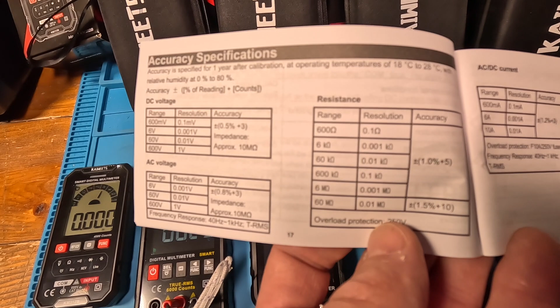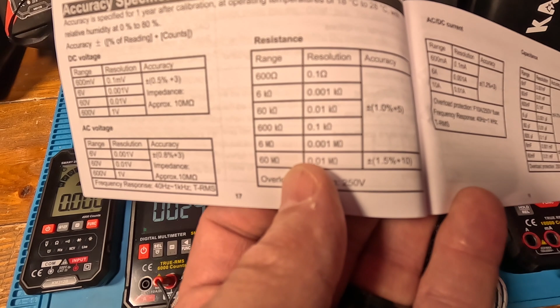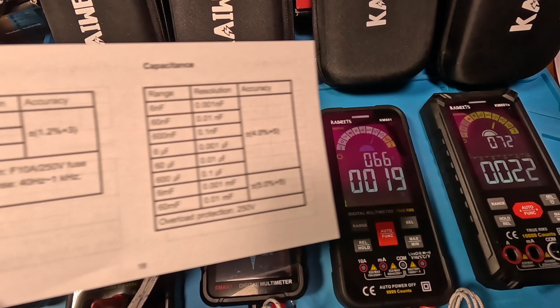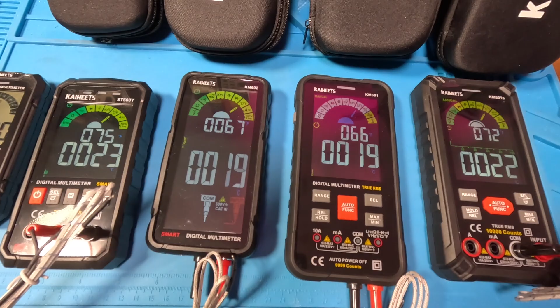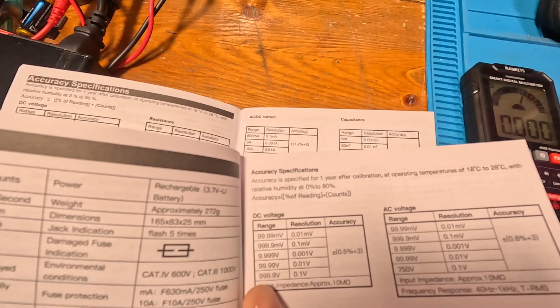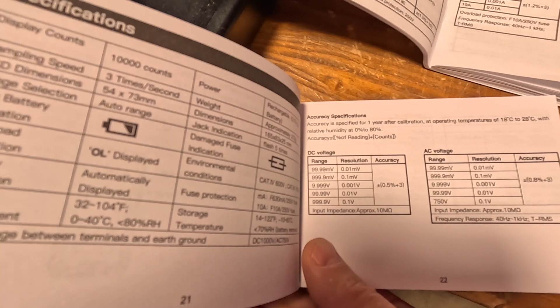Now, you see, there's also the resolution. So you have to look at that. 600 ohm range, you have 0.1 ohm resolution, okay? So there's the thing with resolution as well. Now, one thing I want to point out is resolution on these 10,000 count meters is going to be higher, right? The accuracy is the same, but are you going to get the same readings? No, you're going to get a more accurate reading because of the resolution.